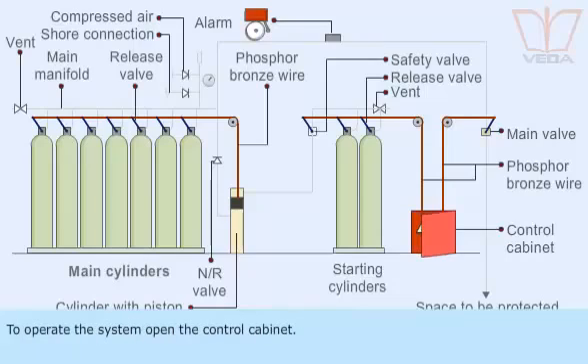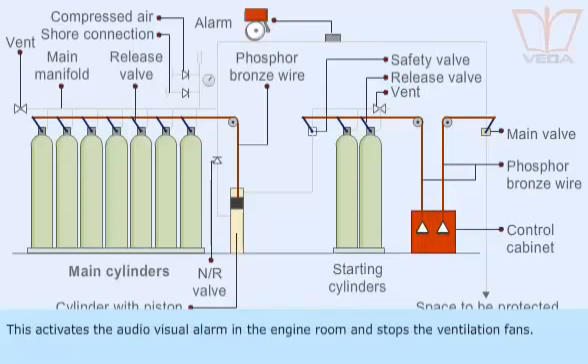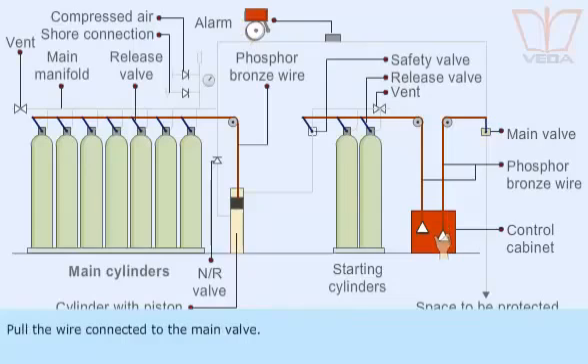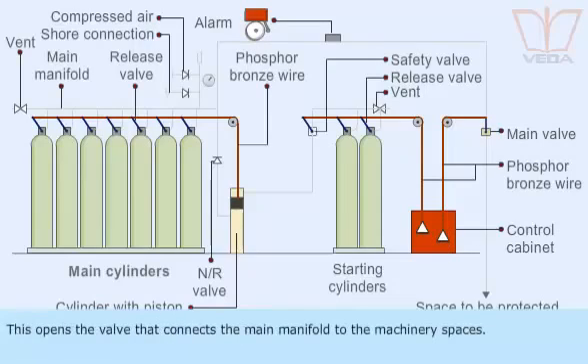To operate the system, open the control cabinet. This activates the audio-visual alarm in the engine room and stops the ventilation fans. Pull the wire connected to the main valve. This opens the valve that connects the main manifold to the machinery spaces.